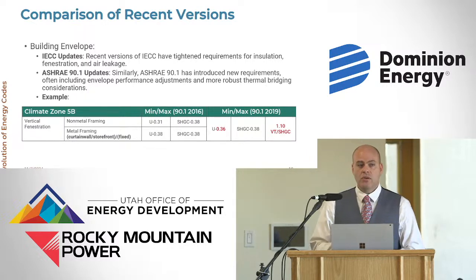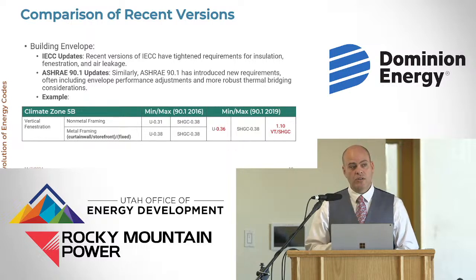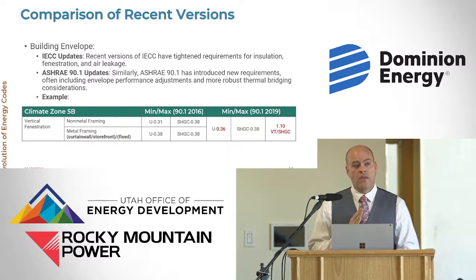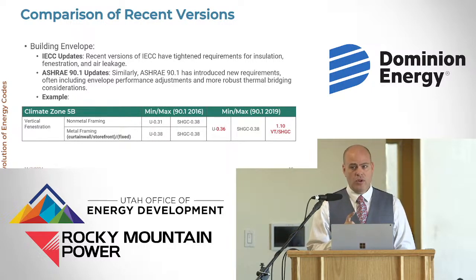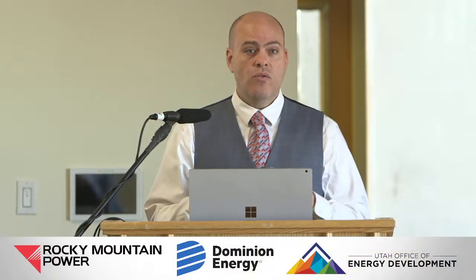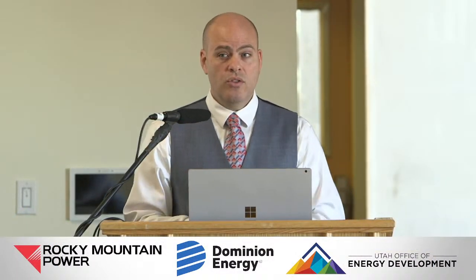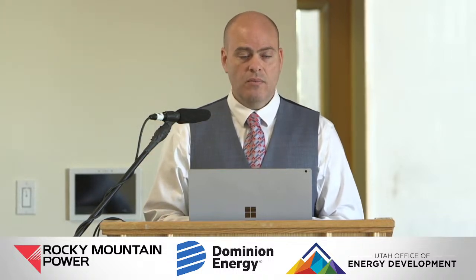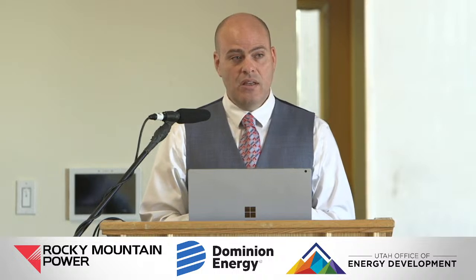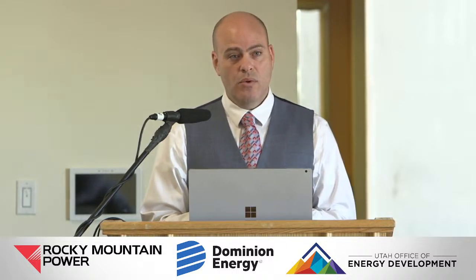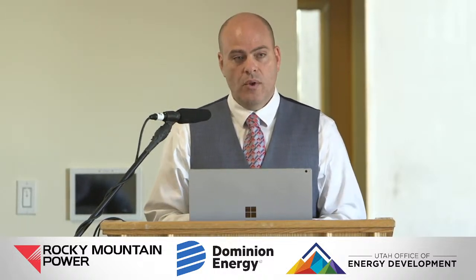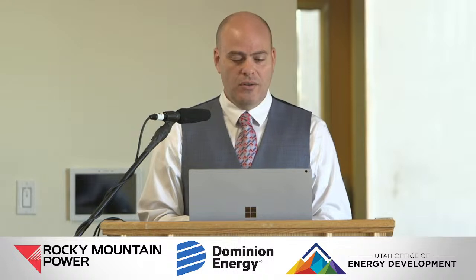The difference between U value and U factor is whether or not, in your calculation for the thermal resistance, you incorporate the frame of the window. The U value of a window takes the U value of the center of the pane of glass that you're putting on the building. The U factor takes the overall assembly of the window into account, so you're using both the glass and the frame in that calculation. That's a common mistake that design professionals make in ComCheck reports, that they'll report the wrong U factor because they'll report the U value instead of the U factor, which makes their project look better in ComCheck, right? Because the U value is lower than the U factor.